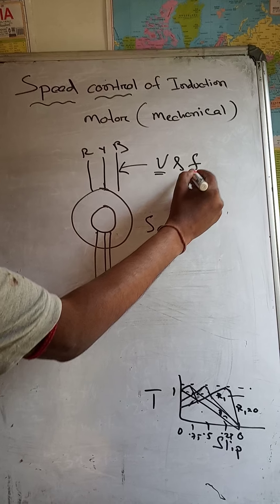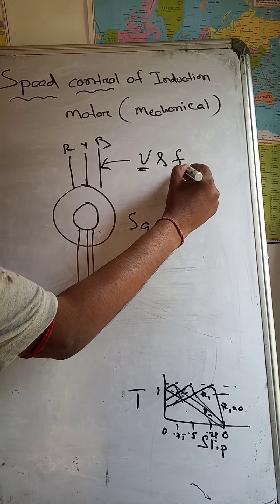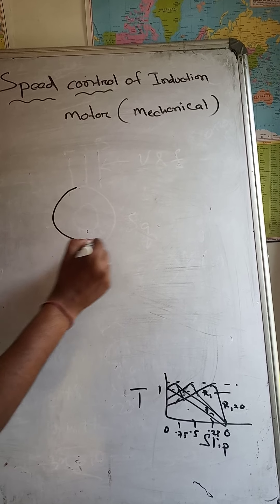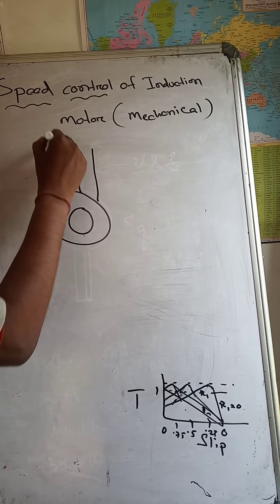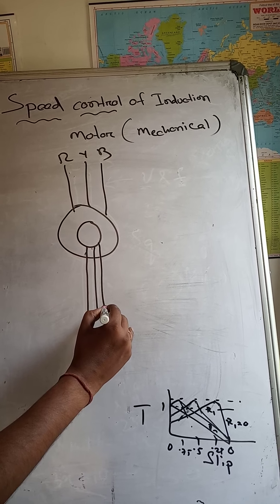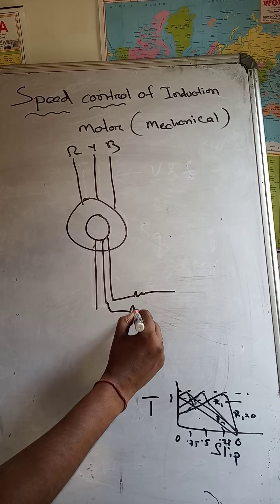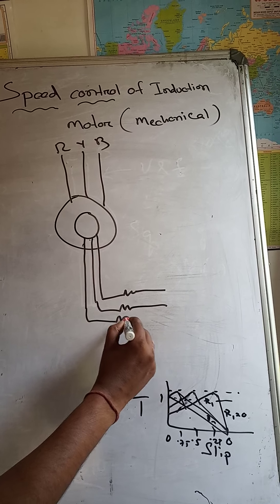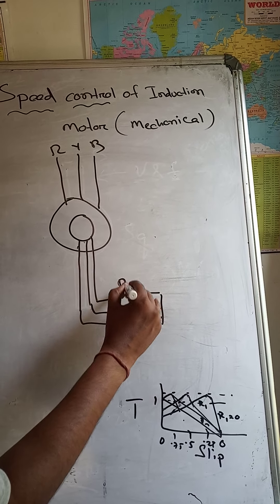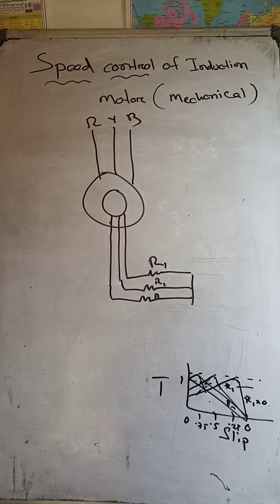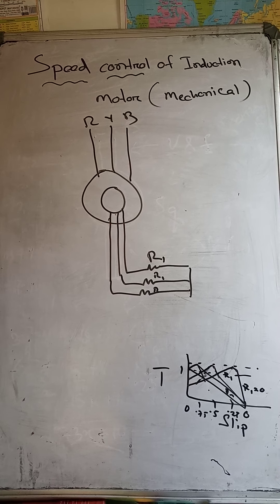You cannot change only the frequency; you must change both voltage and frequency together. In the case of a slip ring induction motor, you can see the rotor is not short-circuited. The stator supply is R, Y, and B. It has a resistance in the rotor circuit. By adding resistance R1 in the rotor circuit, we can change the speed of a slip ring induction motor.